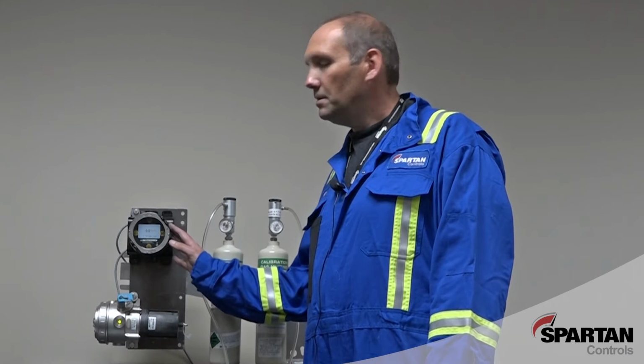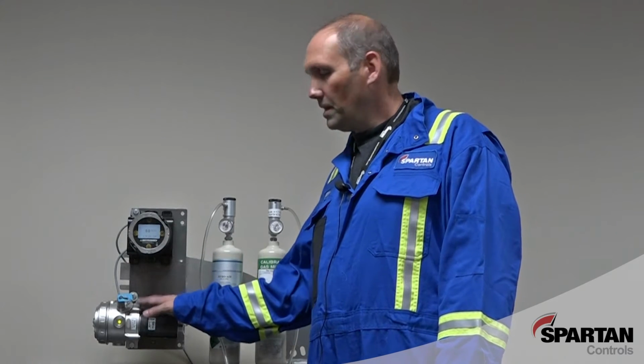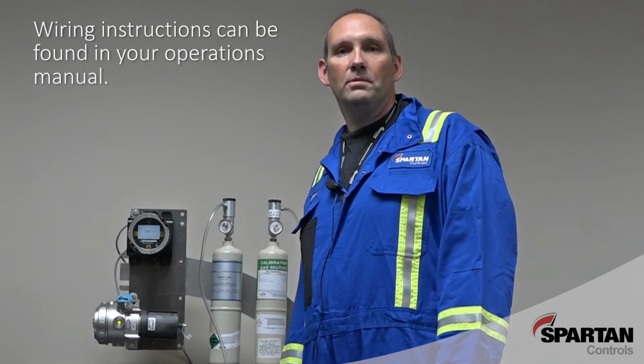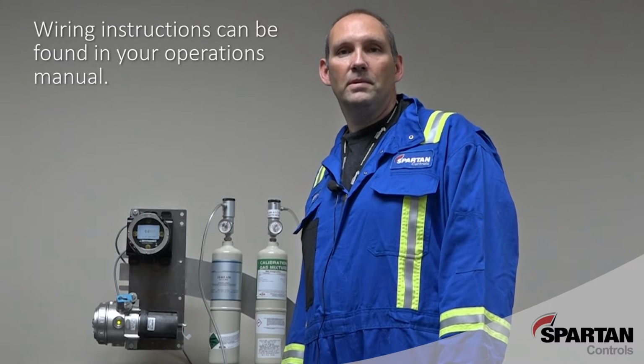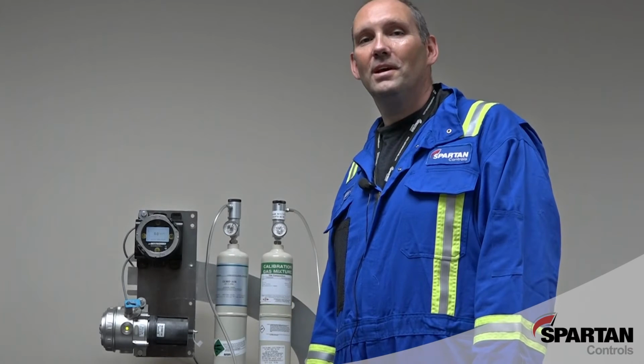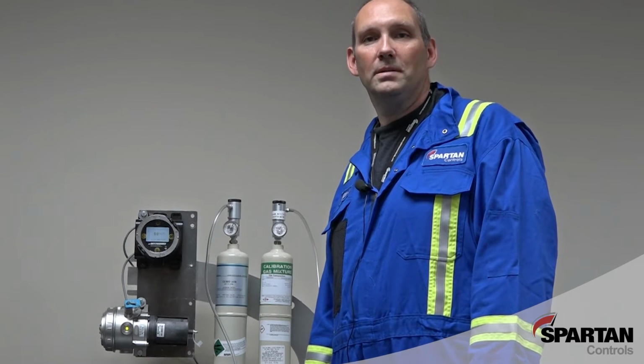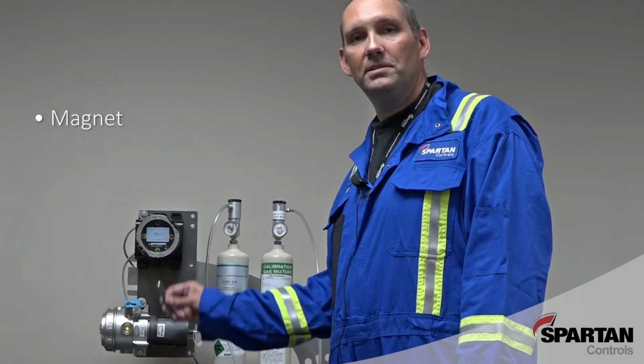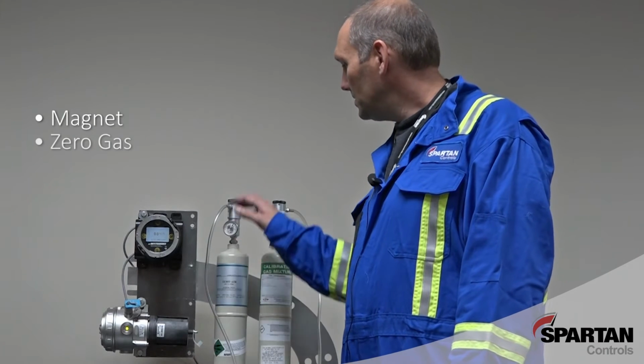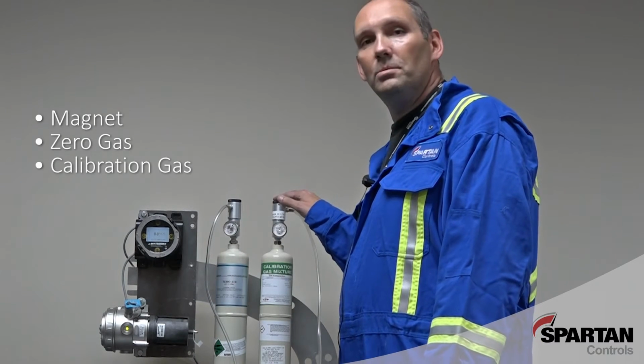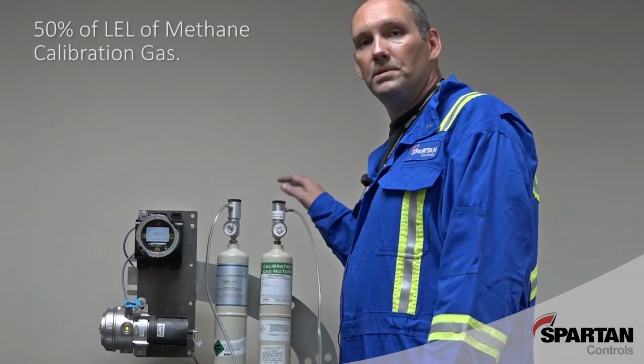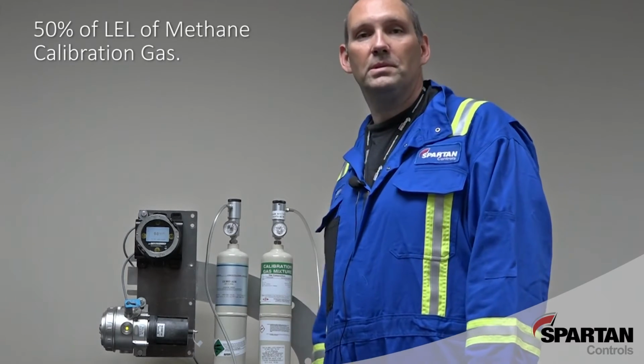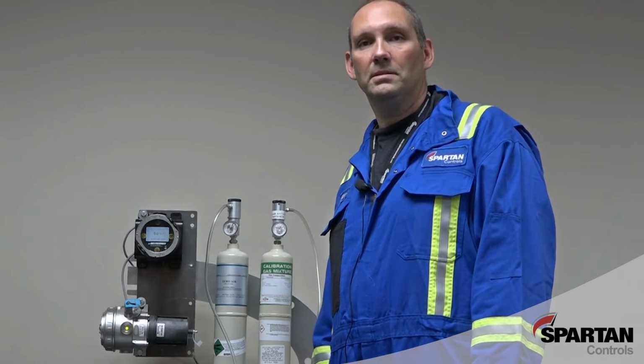Power is supplied to the UD10, which in turn powers the detector and the 4 to 20 milliamp loop. There are various configurations for wiring, and they can all be found in the various manuals. For this calibration, there are some tools that are required: a magnet, as you see here, a zero gas, and your calibration gas. For the purpose of this calibration, I'll be using a 50% of LEL of methane calibration gas.